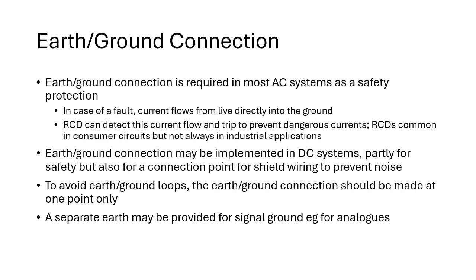And they're used for exactly that purpose. For example, if you had a washing machine and there was a short inside the washing machine, the short would go to the outside of the washing machine, which would make the entire cabinet live, assuming it's a metal cabinet. That would be very dangerous for the user, because if they touched it, especially with wet hands, then they could get a very dangerous electric shock and cause injury or even death. So the RCD would operate within a few milliseconds to trip the circuit and turn off the voltage. Now, we don't often see RCDs in industrial applications. One of the reasons is that a lot of electromechanical devices like motors do have internal earth leakage currents.